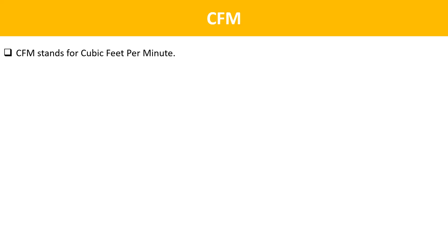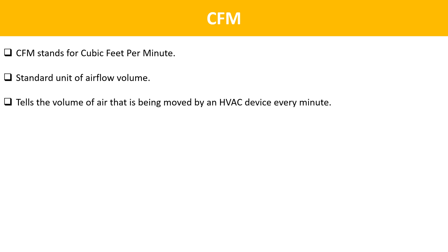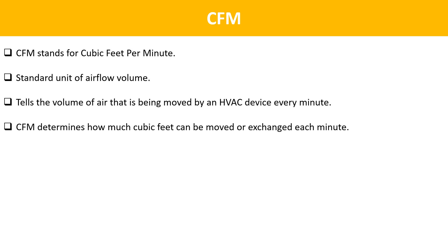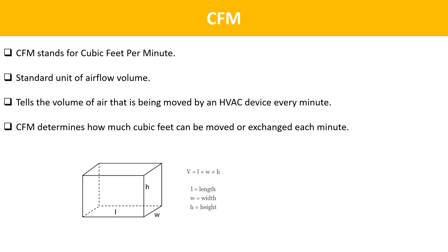The next term is CFM. In HVAC, CFM stands for cubic feet per minute. It is a standard unit of airflow volume that tells you the volume of air being moved by an HVAC device every minute. CFM determines how much cubic feet can be moved or exchanged each minute. A room measuring 1,000 cubic feet would need a 1,000 CFM system to replace all the air each minute.